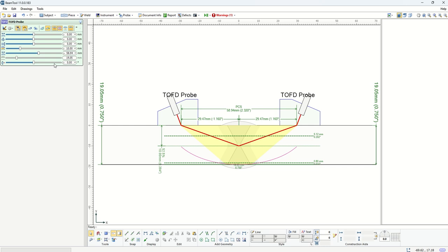Typically, the option that is chosen for ToFD techniques is to have a crossover point be around 2/3 of a thickness. If you come here to this tab, here we have an option to go to specific crossover depths. Either it can be 20%, 66%, 75%.